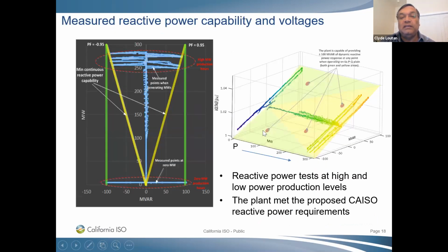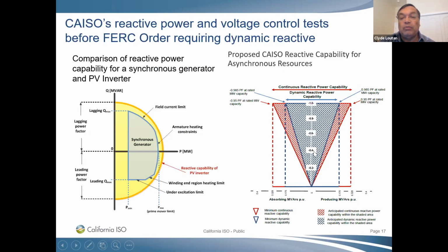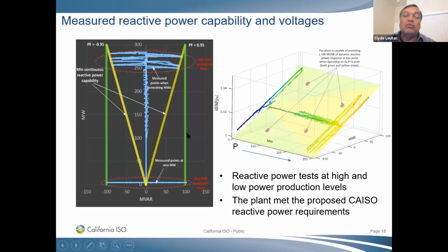This plot here, as I said, is back to the plot on the right. It shows the actual controls when we did that test. So at maximum megawatt output, this plant was able to provide full, and not only reactive, but dynamic reactive. And at 0 megawatt output, or very close to 0, it was also able to provide 0.95 lead to 0.95 lag power factor. So you get almost full reactive control if this plant is really offline or is generating very, very little actual megawatts.